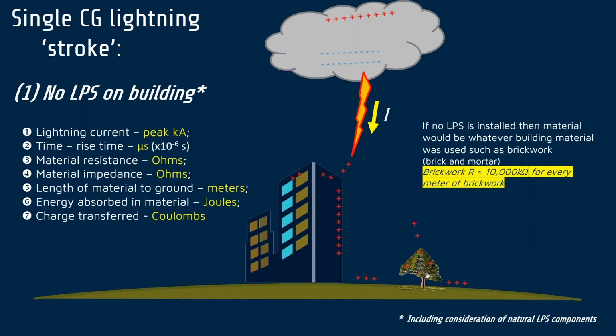Okay, before I get further digressed in that, let me come back here to those formulas we talked about, and what we have to build this assessment. You've got lightning current, peak kiloamps, the rise time in microseconds, the resistance of the path, so in this case it would be brickwork, also the impedance. If there are any metallic components, they need to be considered in series and parallel. Then the distance from top to bottom, because the further it is, the resistance and impedance will increase. And then the amount of energy that's actually being absorbed.